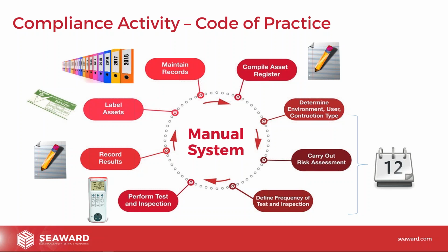Maintain the records, so we end up with a big load of PAT testing records, paper records going back to the year dot. And we maintain those records, so when we get new equipment, we add those to the list. Old equipment we take off the list, and that sort of thing. And then the whole process goes round and round again, and that effectively is a manual system. That's generally PAT testing. So it pretty much goes round that process, and you go back. You keep your asset register up to date. You reassess the risks. You perform the inspection and test, record the results, label the assets, and then every so many months or so many years or whatever it is, you just keep going around that cycle.